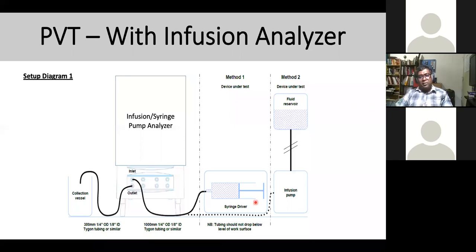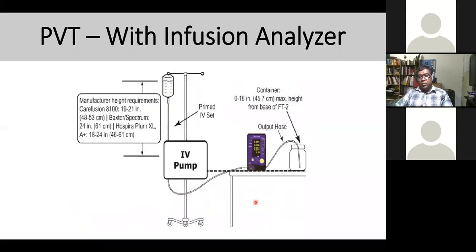Another, second method of connection, you can see with the IV pump and the SimCube, using another type of analyzer. It is giving the flow line, and it will monitor the same thing. So you can monitor flow, occlusion pressure, and time.